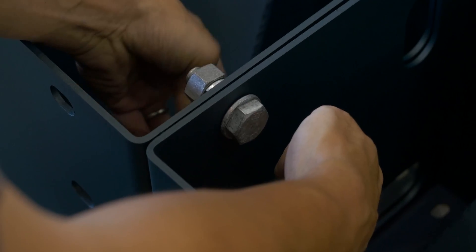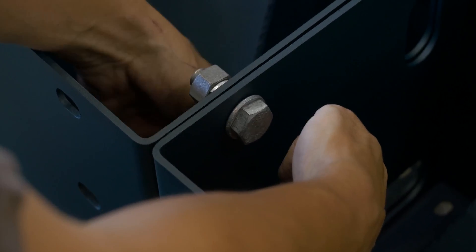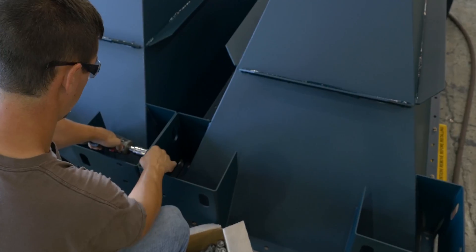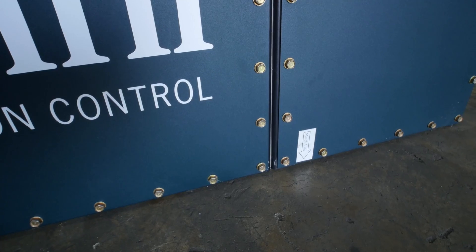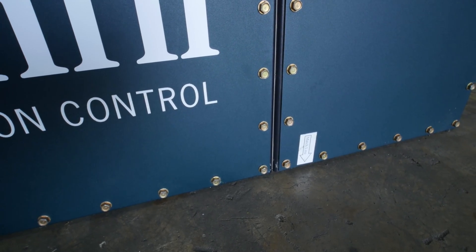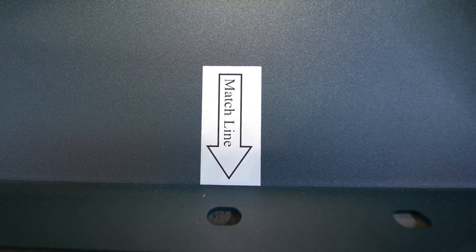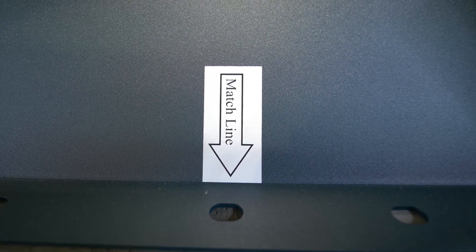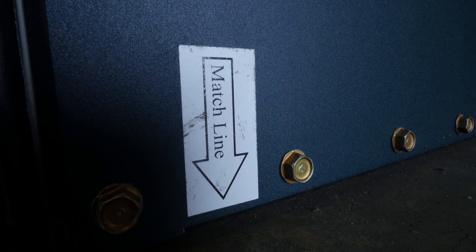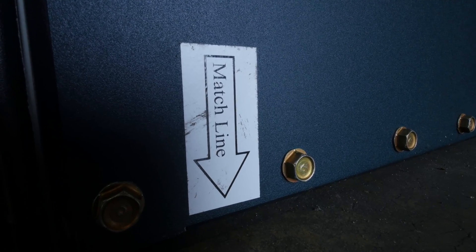On collectors that have half frames, the filter module to hopper bolt holes are not symmetrical. Match line labels are provided on the filter module and all hoppers. Turn the hopper or support structure assembly so that the match line labels on the hoppers line up with the match line labels on the filter module.